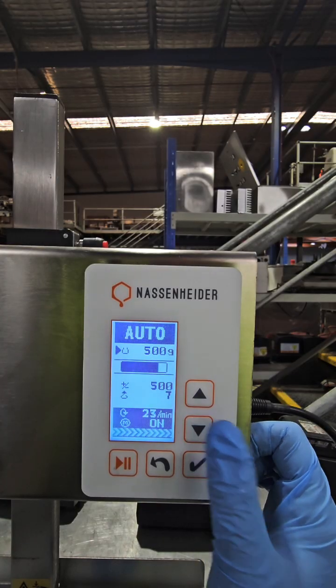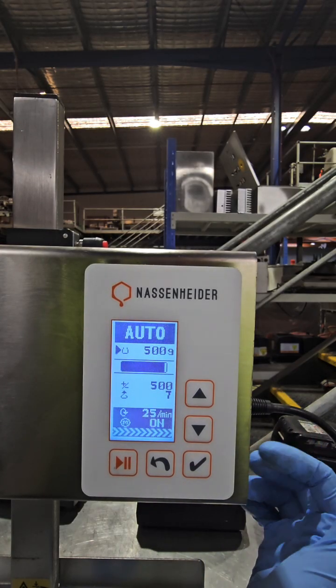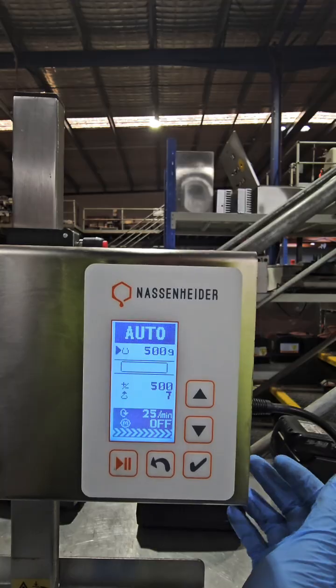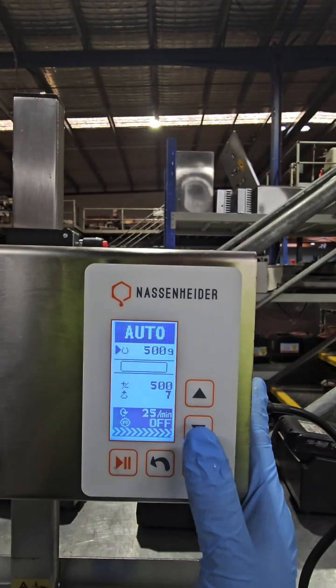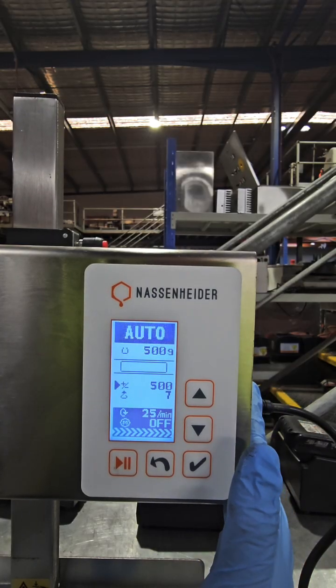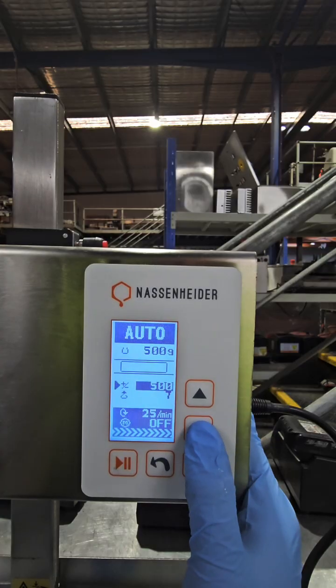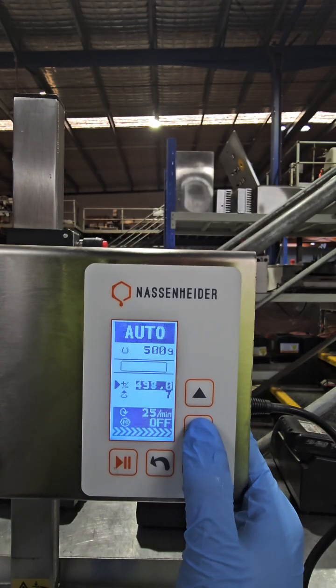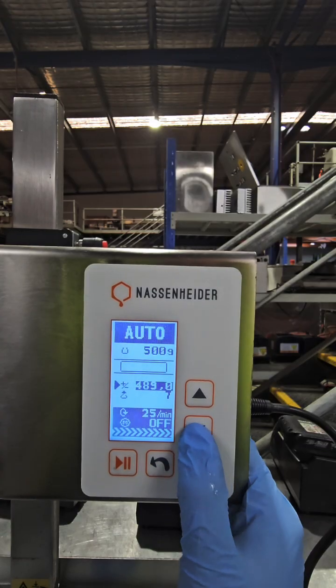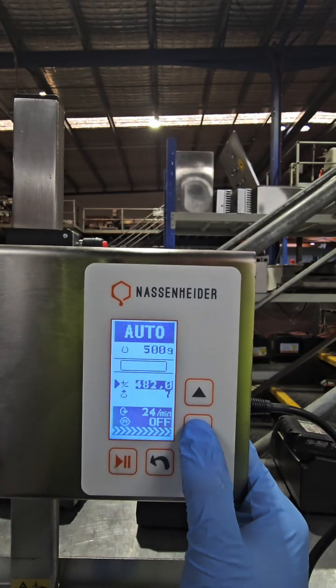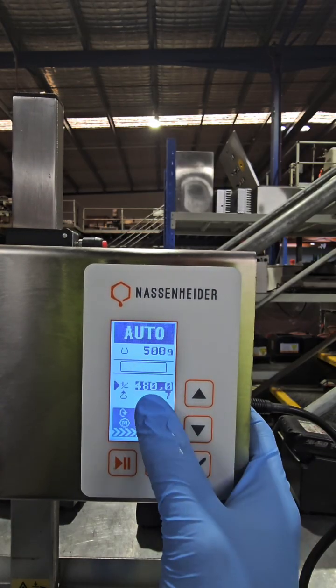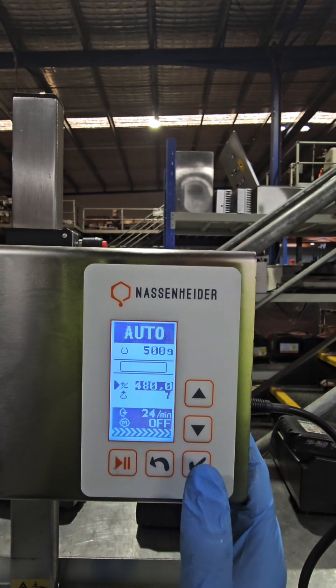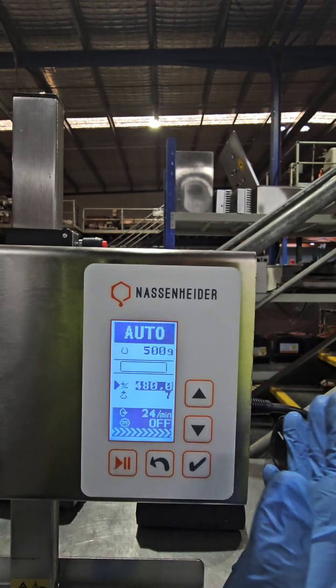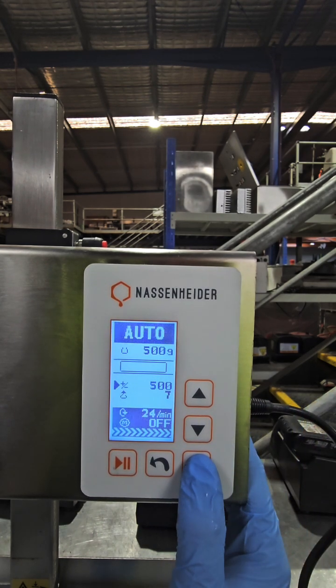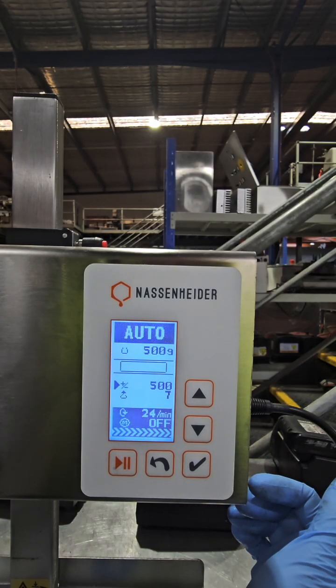However, if you get a deviation, say you only filled 450 gram, you filled over or under by X amount of gram, what you then do is you go to the plus and minus section here, and you enter exactly how many grams you have dispensed just now. Say you dispensed 480 and you want the 500, you just select the 480 that you have dispensed, press confirm, and the pump will recalibrate itself to fill 500 gram the next time.